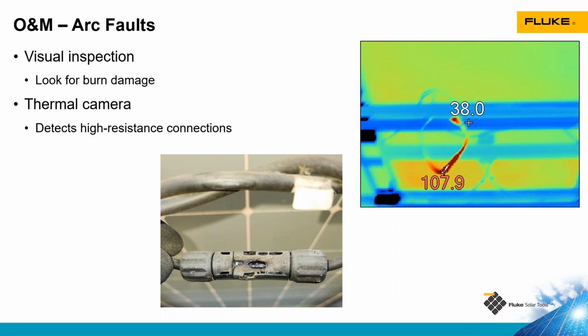Thermal cameras can be used to find arc faults because if it's faulting pretty badly, it's arcing there and that's releasing heat. So I'm not necessarily looking for a specific number, but I'm looking to see how that connection compares to other connections in the system under the same environmental conditions. So I can't go out one day, get some pictures, go back a different day where the environmental conditions are different and expect to get good results.